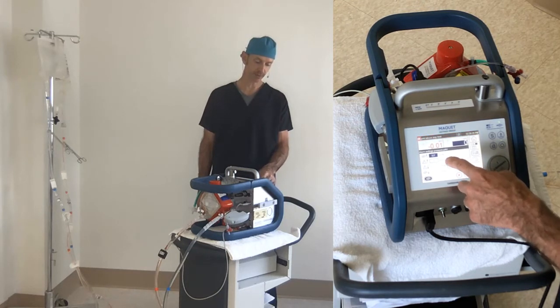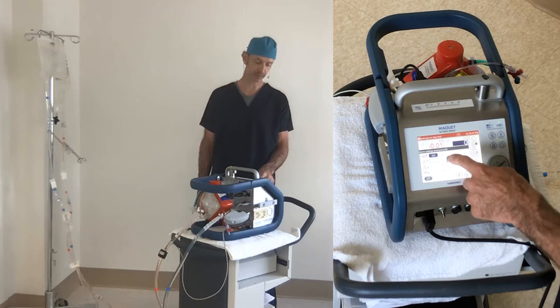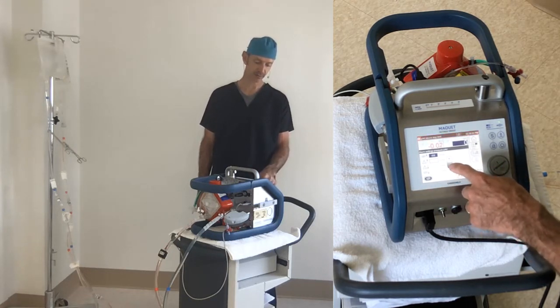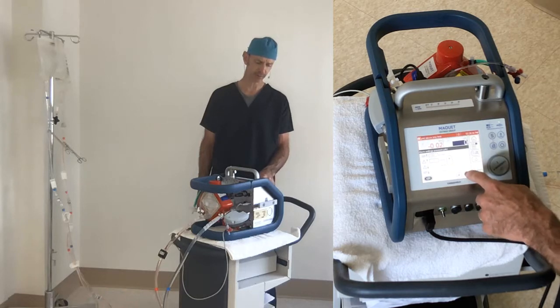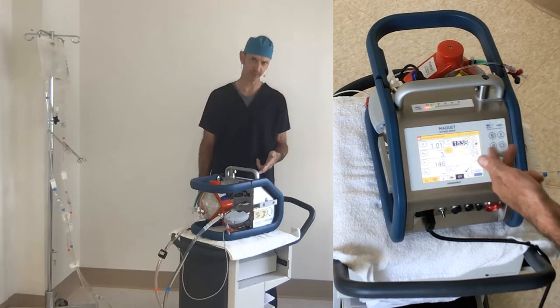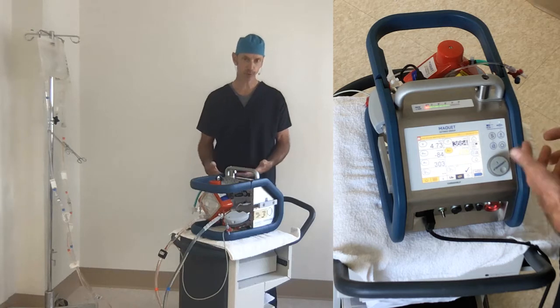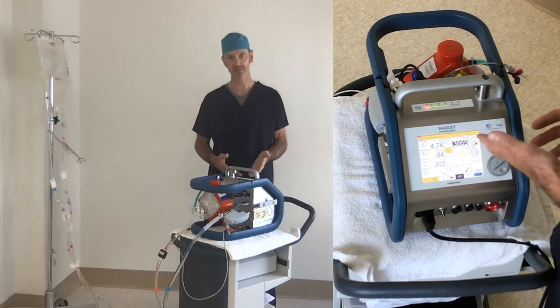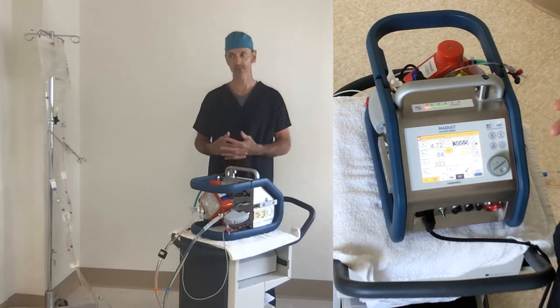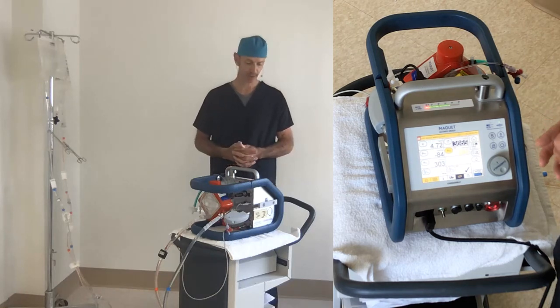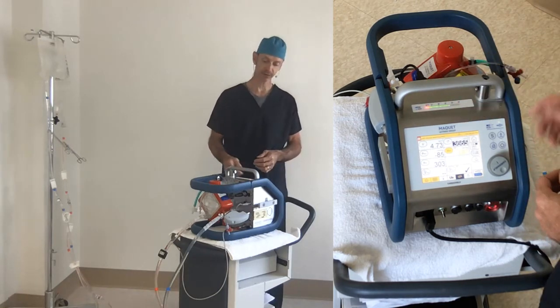So the moral of the story here is you could get called to the bedside because the pump won't run, and it seems unreasonable for the pump to not be running because you're expecting normal limits to be set in here. But if inappropriate limits are set, like stop the pump if the pressure is greater than 50, the pump's going to stop. And get a red bar across the top and you have zero flow.